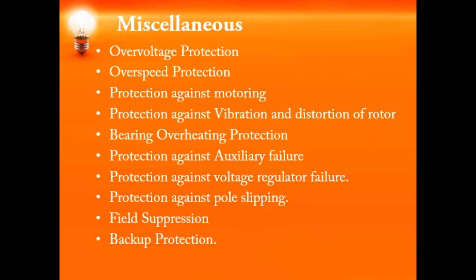So we use a definite time DC overcurrent relay which will operate whenever there is an overcurrent in the rotor, and in such a situation the excitation will be switched to a predetermined value for manual control. We need to use an under voltage relay if we are going to protect the transformer also. So for different types of generator sets, we use different types of relays.